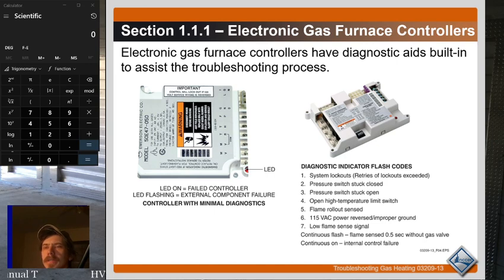So there's almost always a code that says, hey, your polarity is reversed. Or if the board doesn't seem to be working right at all and it's brand new, try switching the polarity. Maybe the wires are hooked up wrong. So just because black is supposed to be hot and white's supposed to be common, doesn't mean that somebody didn't accidentally reverse the wires somewhere in the electrical circuit, okay?